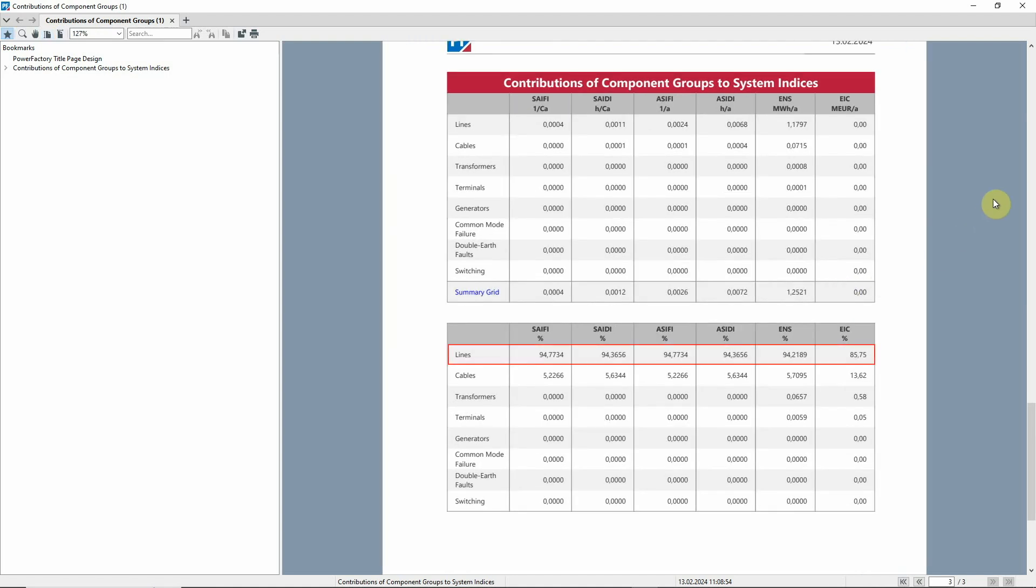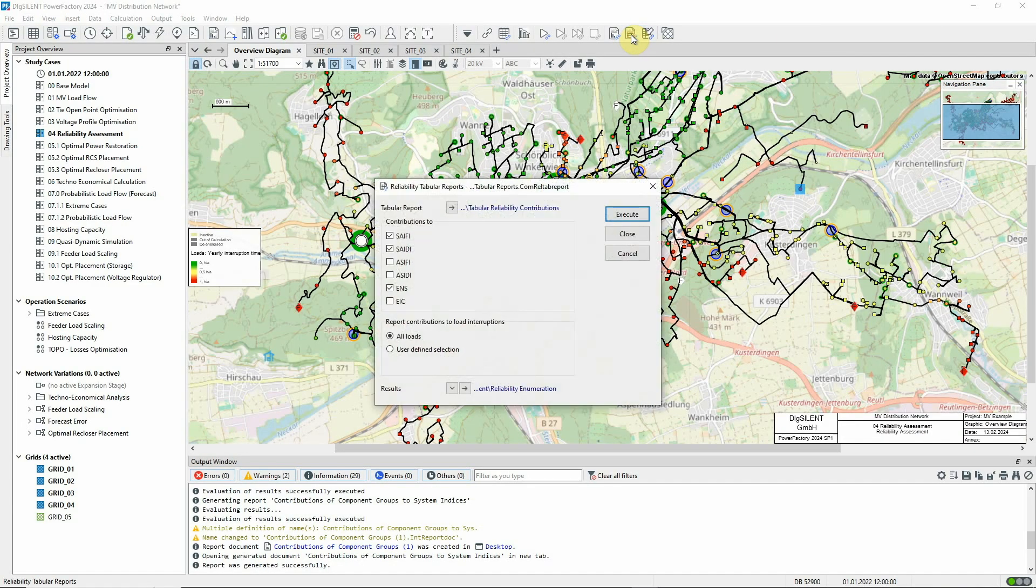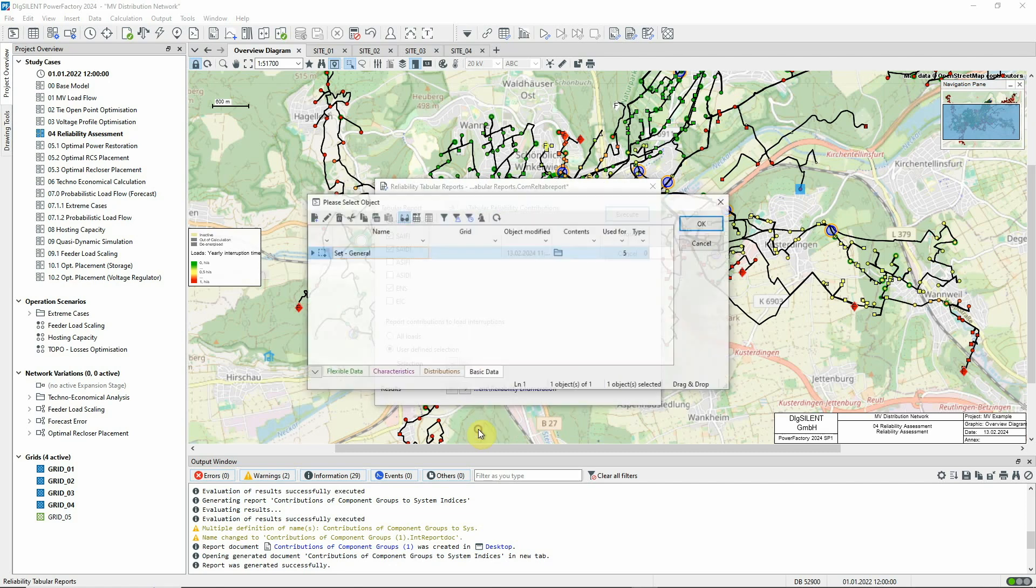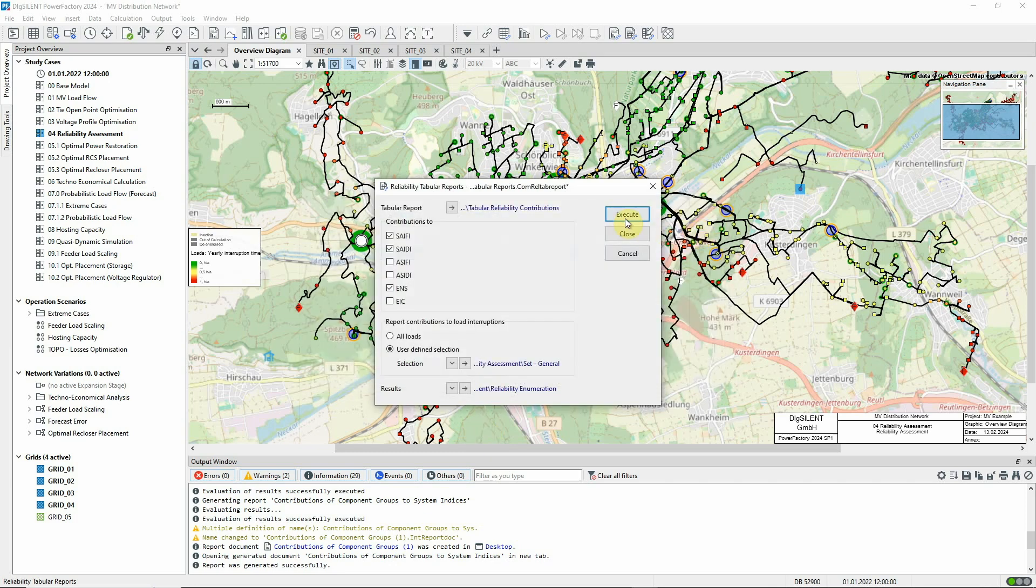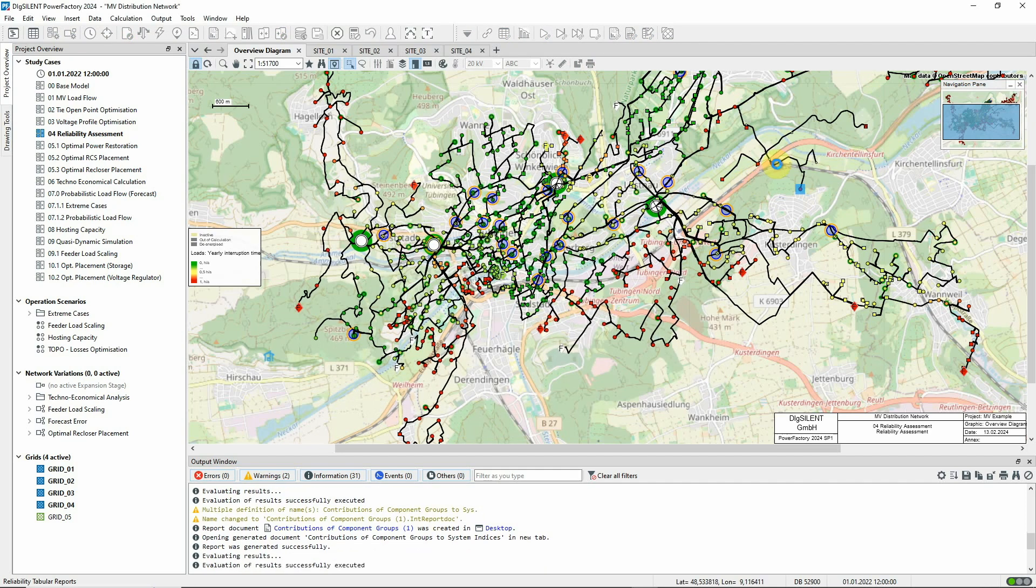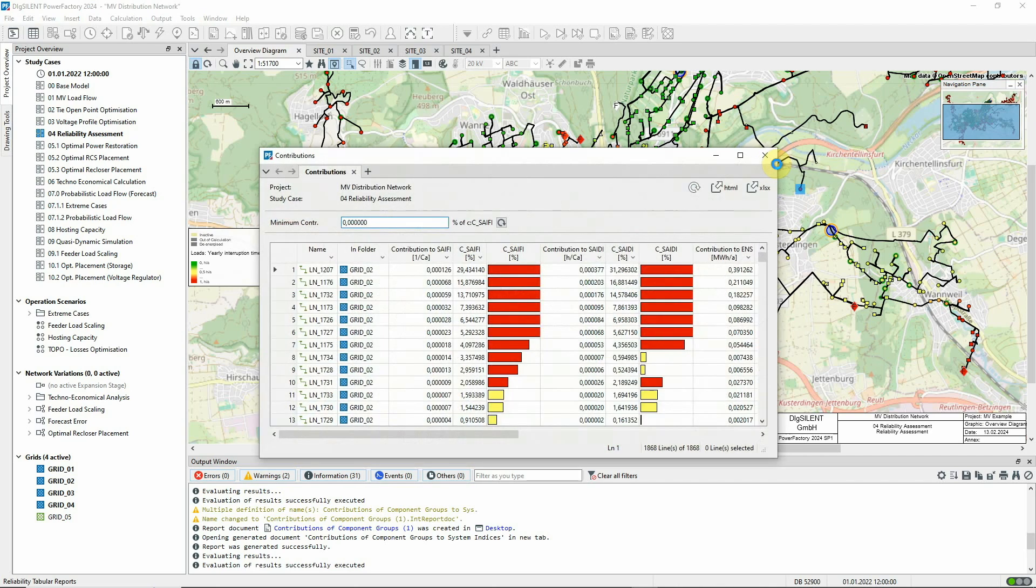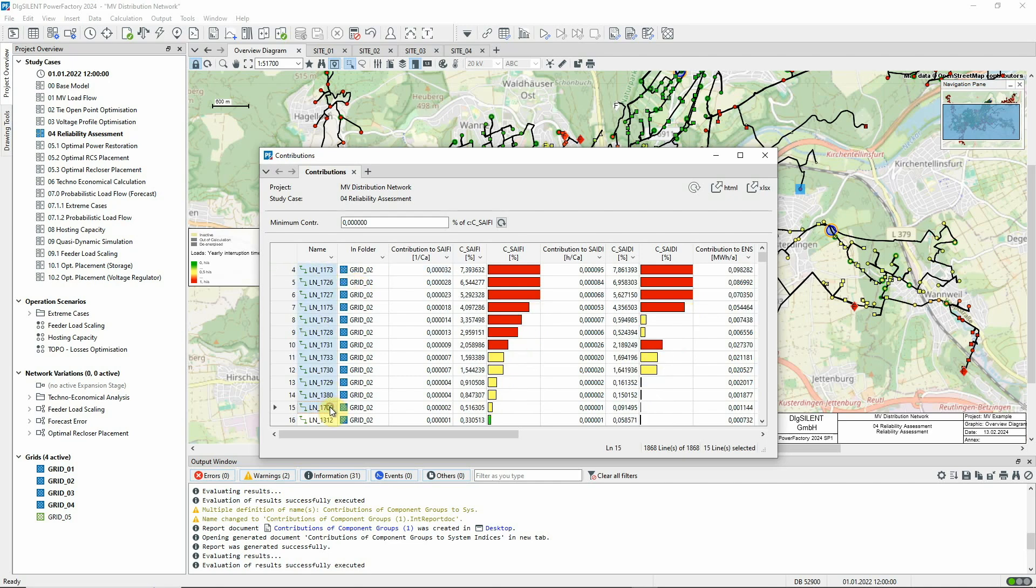We can see that overhead line faults are the major cause of loss of supply for these customers. Let's now generate a tabular report of contributions again. This time, we'll just report contributions relating to this load. Faults on these elements contribute most to the average interruption frequency.